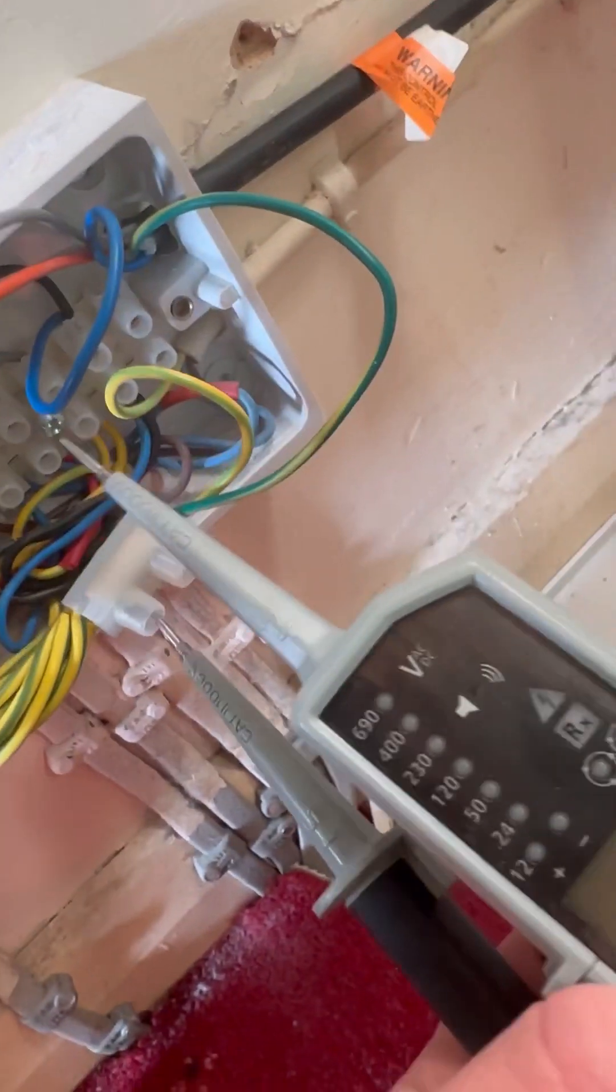So we'll go for it a bit more in depth. Switch live wire only hot water on. So what that means is we don't get 240 on gray if the programmer's doing its job properly and the cylinder stat's okay.